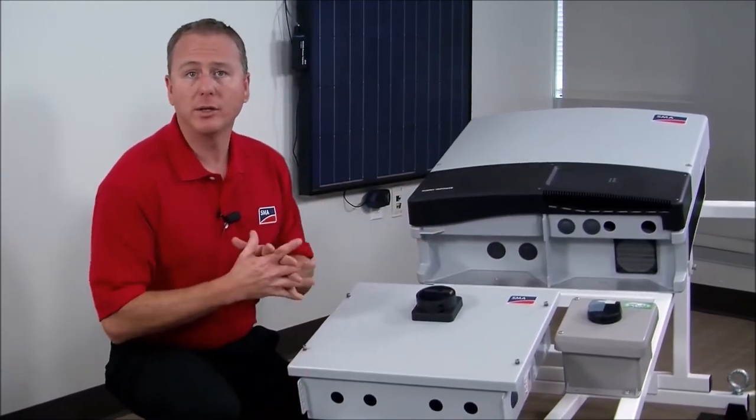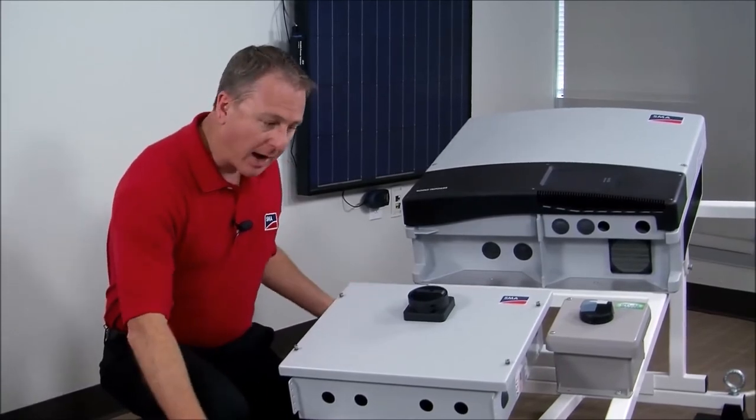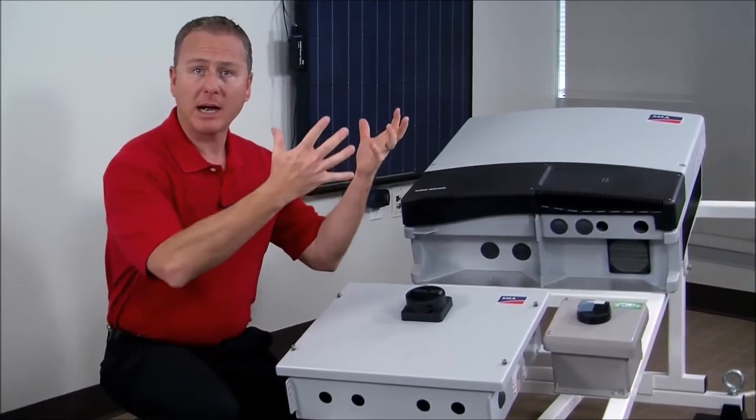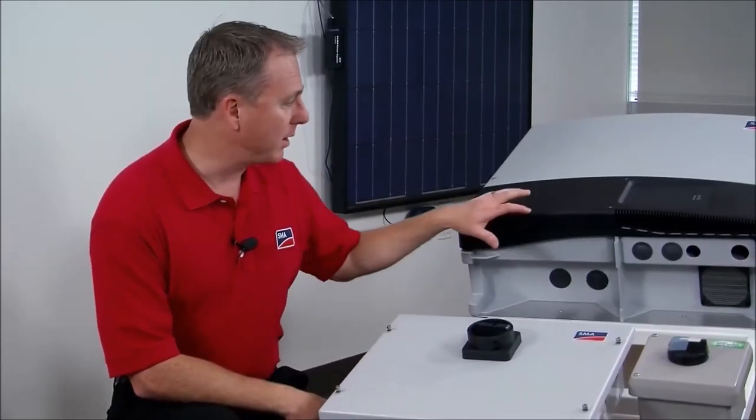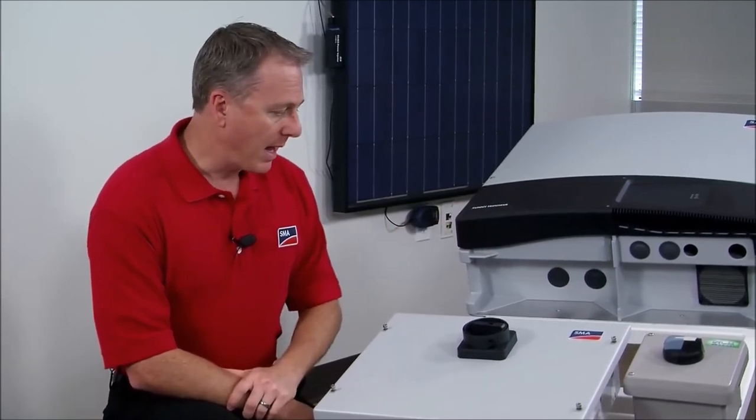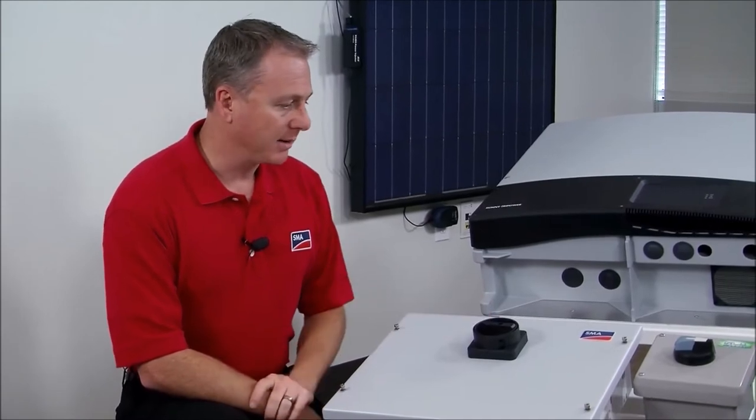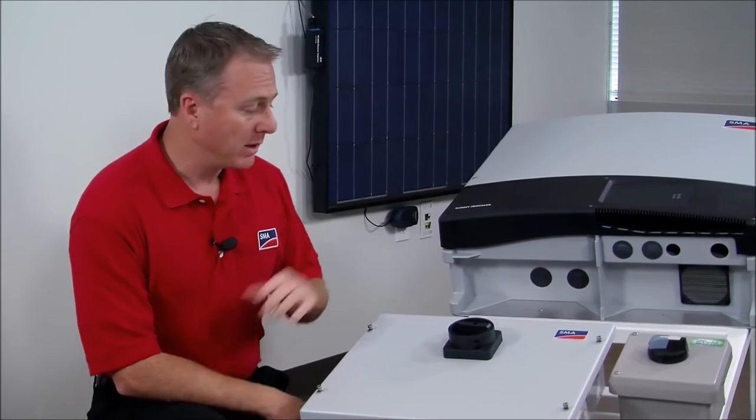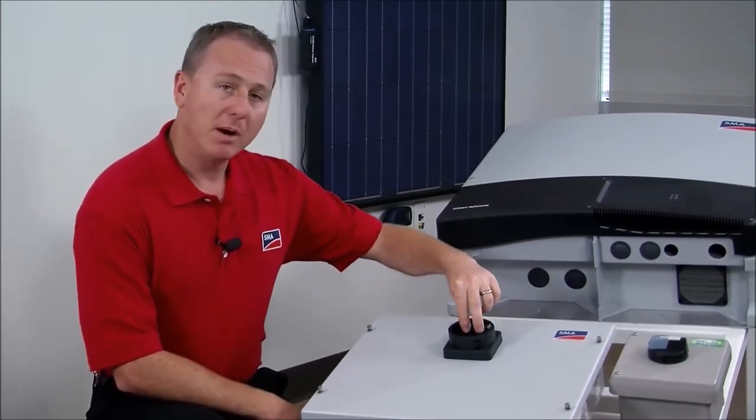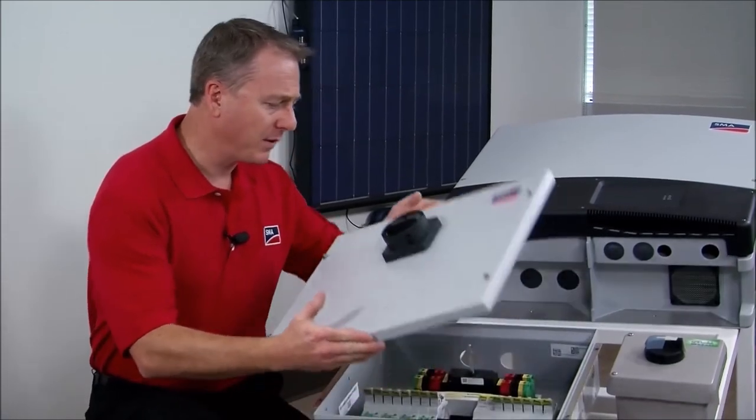Matter of fact you could do this on the ground level and then using the eyes you can crane up the entire unit to the roof and then place it next to the array. I have an SMA DC connection unit mounted underneath this tri-power and it is a combiner box with a DC disconnect. Now we'll take the four screws off using a four millimeter hex wrench. The DC disconnect must be in the off position and we just lift the cover off.